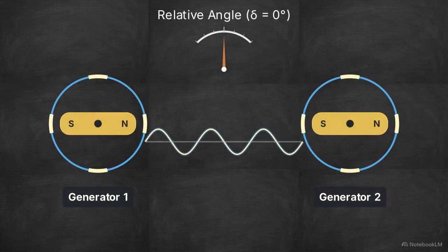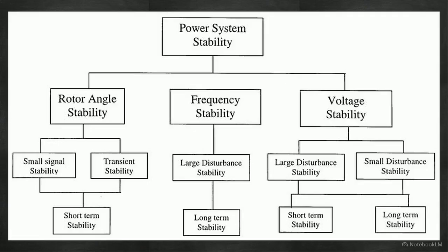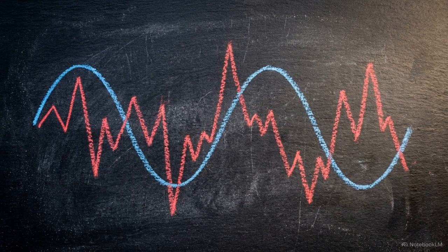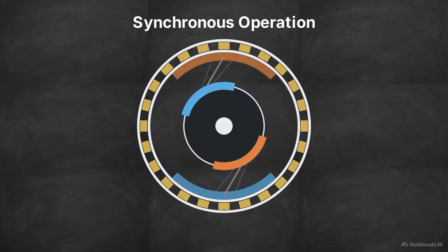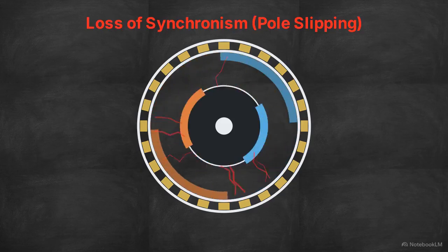This is the fundamental ability of interconnected synchronous machines to maintain their shared rhythm and return to a steady state after a disturbance. Engineering standards categorize stability based on the size and timing of the shock. Our focus is on the most violent category, large disturbance transient rotor angle stability. During an unstable transient, the grid physically desynchronizes. The heavy rotating machines that generate power lose their magnetic lock with the rest of the system, resulting in a total loss of coordination. Understanding grid collapse requires viewing the electrical system as a massive, interconnected mechanical web.